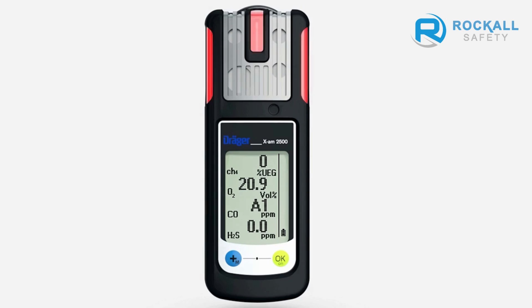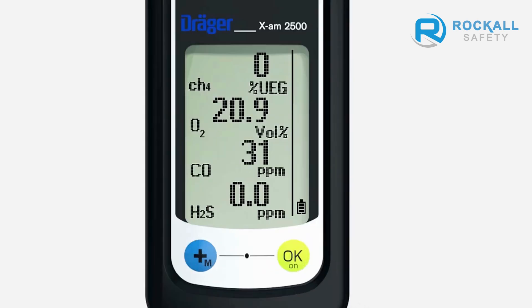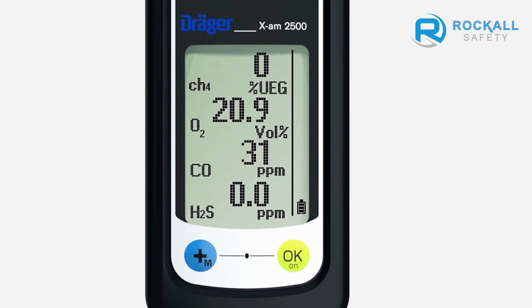The audible, visual, and vibration alarms are all activated periodically. A1 alternates in the display with the gas concentration. An A1 alarm can be acknowledged by pressing the OK key. The alarm automatically stops as soon as the concentration drops below the defined threshold.